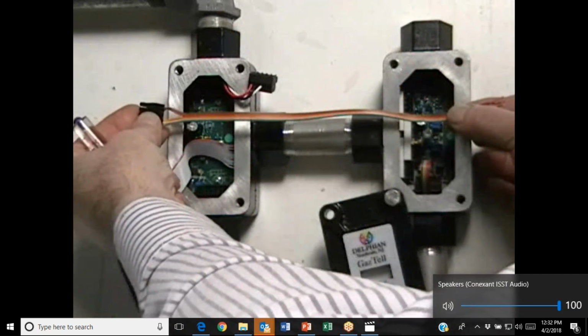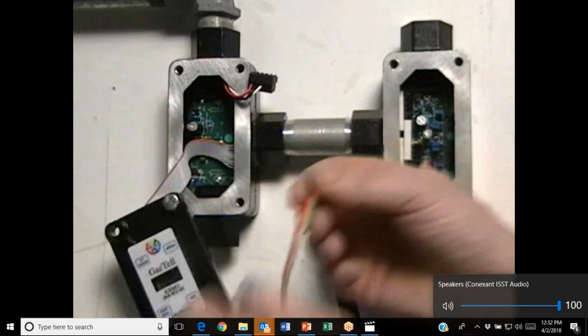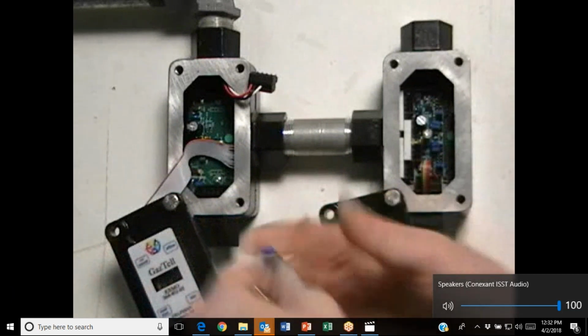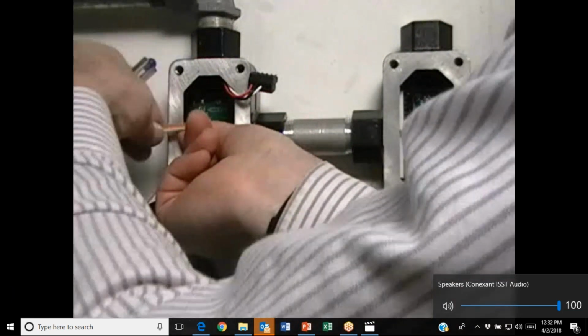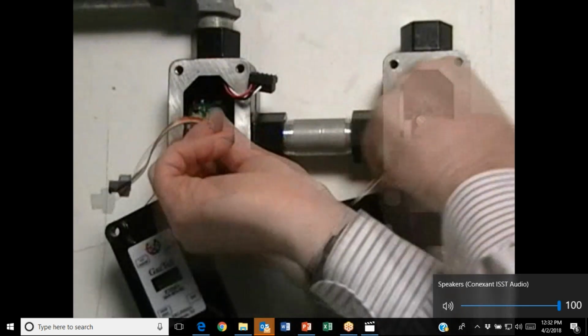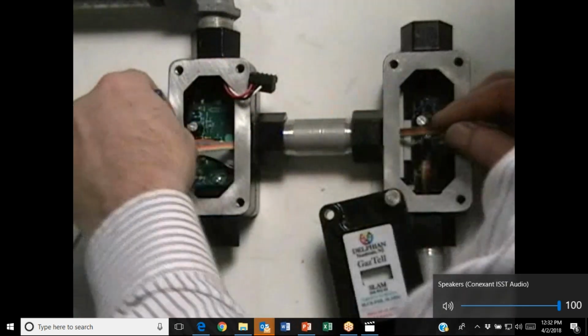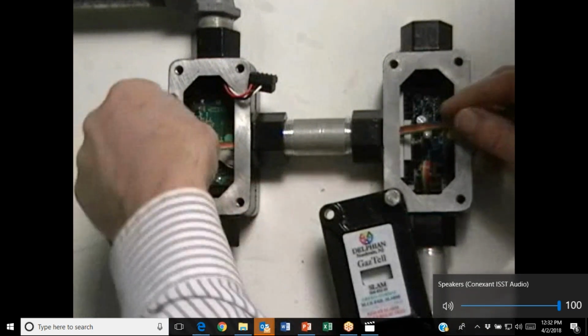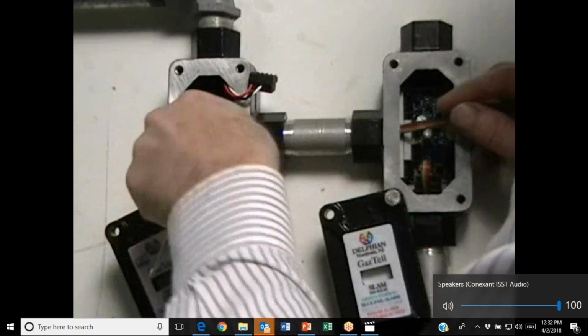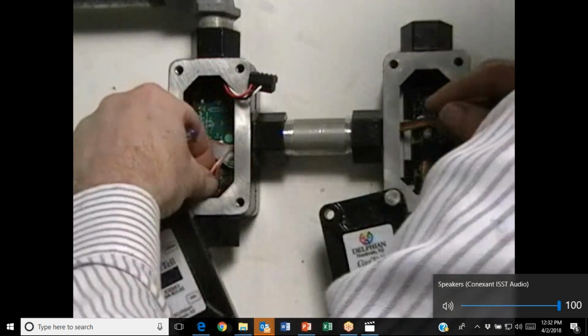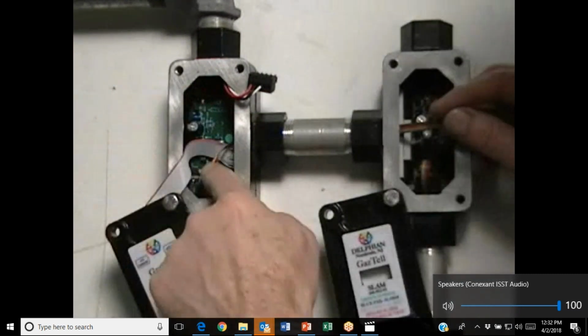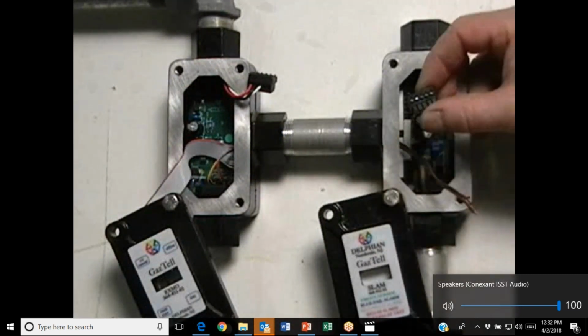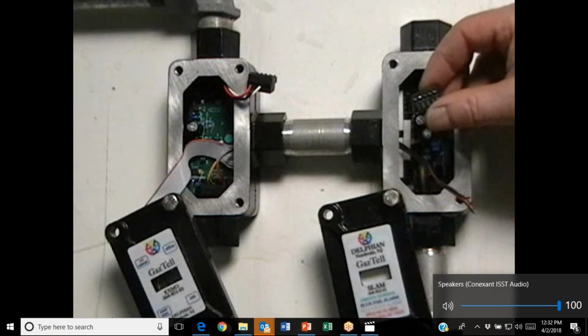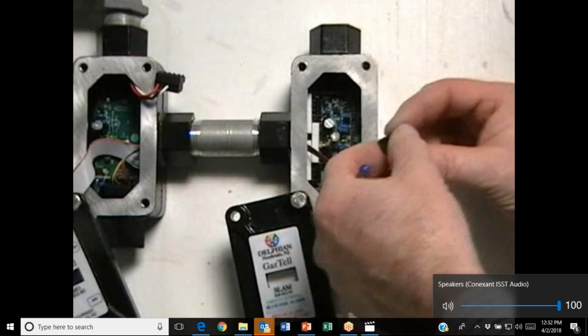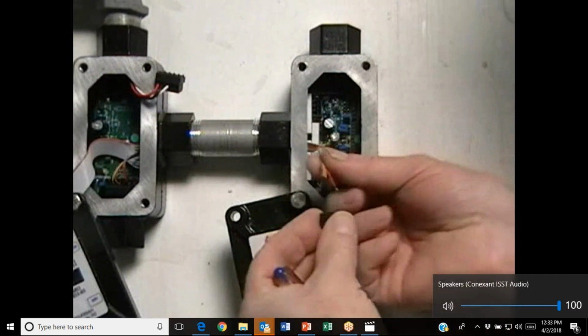These modules can be mounted up to 400 feet between each other and the detector head. Once the components are mounted, wiring them up can be accomplished by pulling a 5-conductor cable between the individual modules and 2 or 3 conductor cables for power supply and signal out, then terminating using the supplied 5-pin terminal block. In this video demo, we have used short lengths of conduit, therefore short wire runs, but you will need to pull the cables through the conduit using the typical pulling techniques.